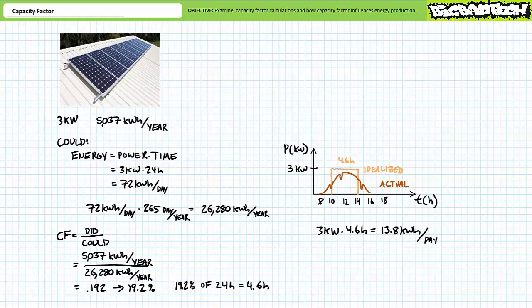For solar resource measurement, the span of time is what is commonly referred to as peak sun hours, which if you think about it is just another method of expressing capacity factor. 4.6 hours is 19.2% of 24 hours. Express using the time format, peak sun hours just makes it easy to quickly estimate the average output of a solar array of a given size.